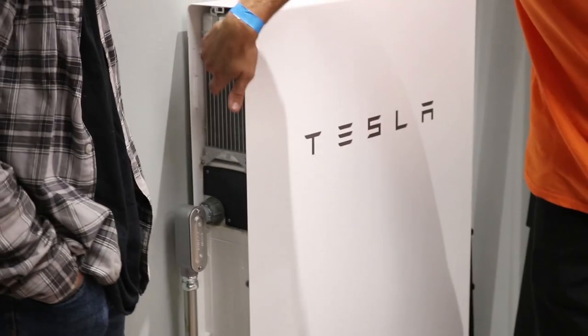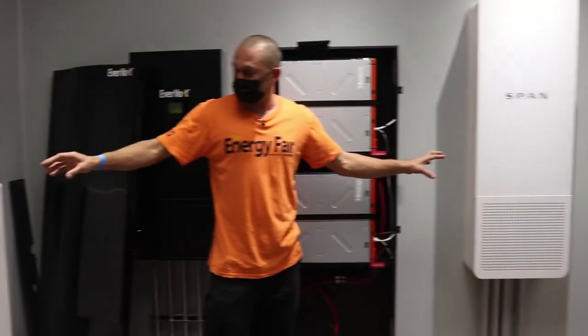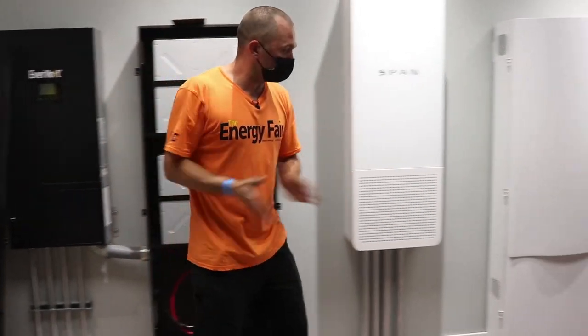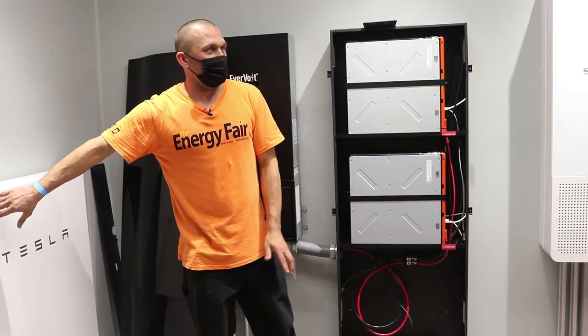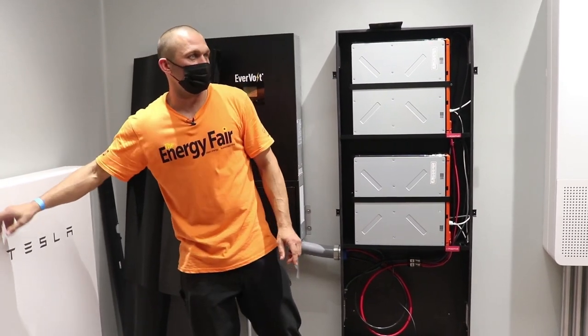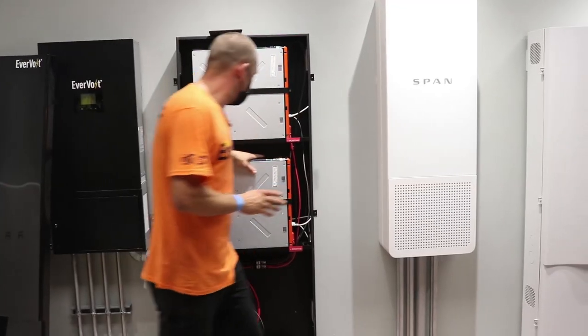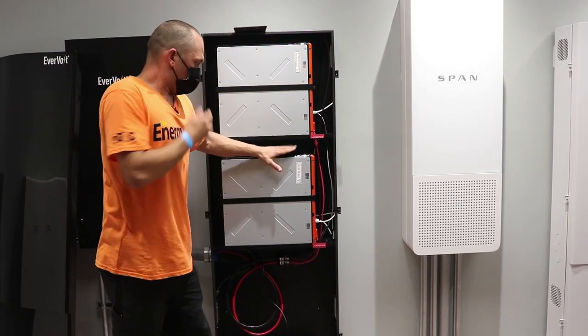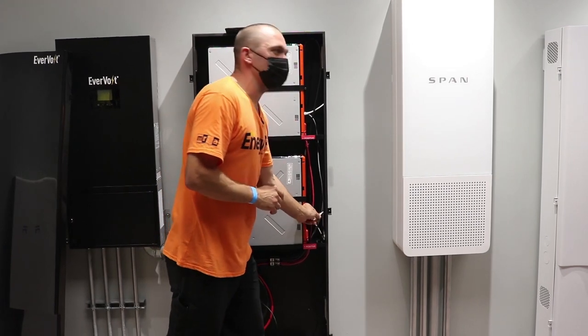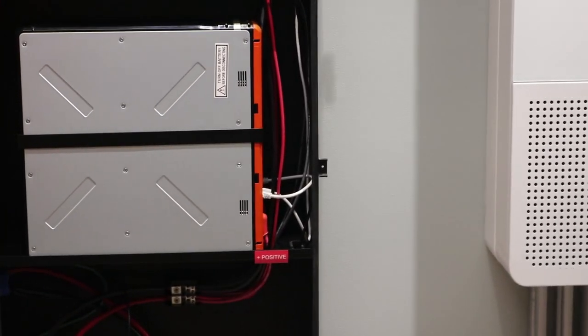They took the side panel off if you want to look at that later — it's pretty cool. Sometimes people call these an 'AC battery' because you just plug AC in and get AC out. But inside there's actually an inverter-charger that steps down to DC, because the batteries are still fundamentally DC electrochemical. With these lithium-ion battery banks — quite different from old lead-acid — there's a CAT5 cable connecting each battery together and going back to the inverter.